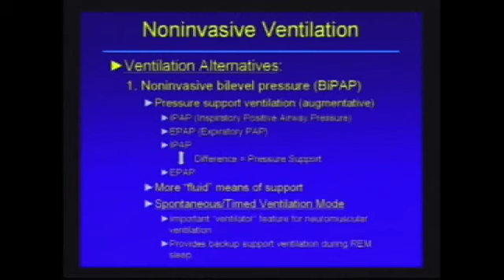This is, again, that ventilator feature where you have the timed backup mode, and it provides you with that backup support. Now, these are just 3 different types of bilevel pressure systems, all of which have backup modes in them. And we just want to talk about the features just a bit. What's really important when we set this up, as opposed to people in the hospital who are on a ventilator and usually sedated and not aware of what's going on, is that people use this while conscious. So it's really important to get that system in synchrony with your breathing pattern so that there is good support without you feeling like the machine's controlling your breathing. It's just augmenting your breathing.